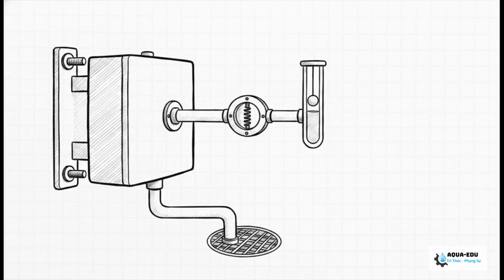Time to mount the wall bracket. Secure it using heavy-duty anchor bolts, ensuring the whole thing is perfectly level. Then, go ahead and route the white and blue sample line from the main RO feed. Now, this line must go through the brass pressure regulator to appropriately drop the pressure for the flow cell and then through a flow control valve.